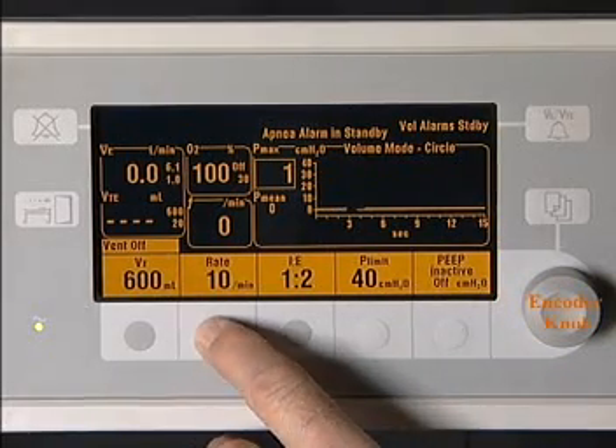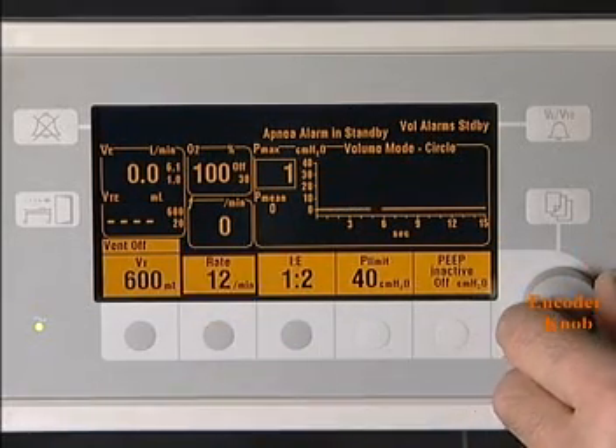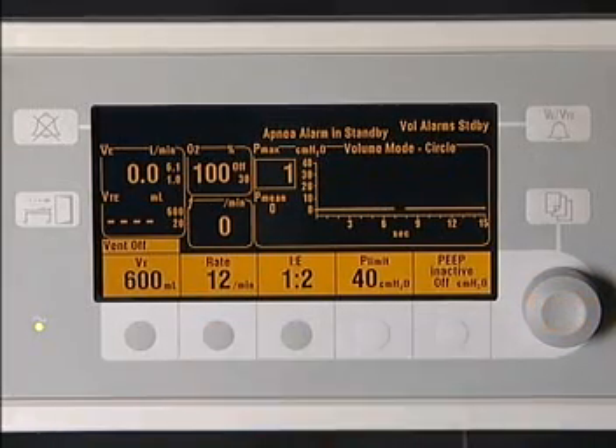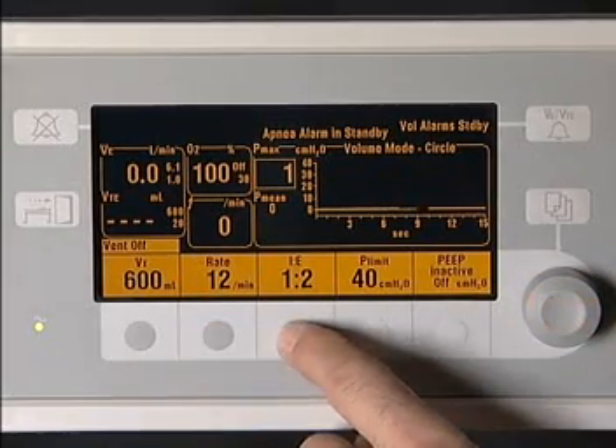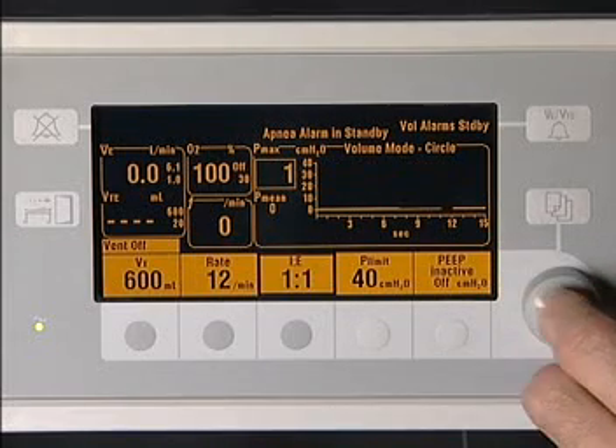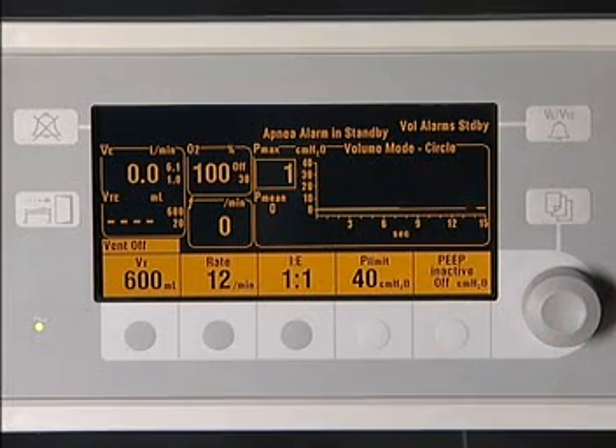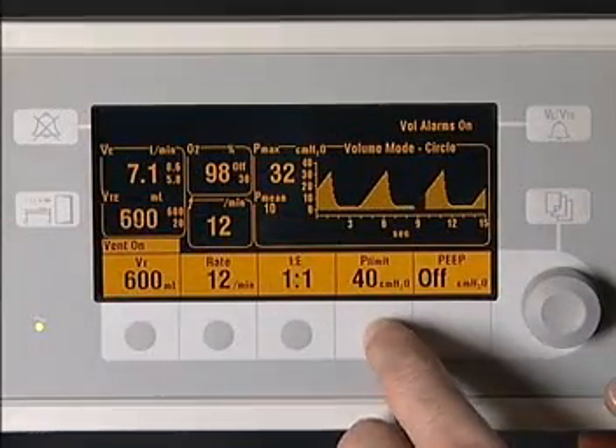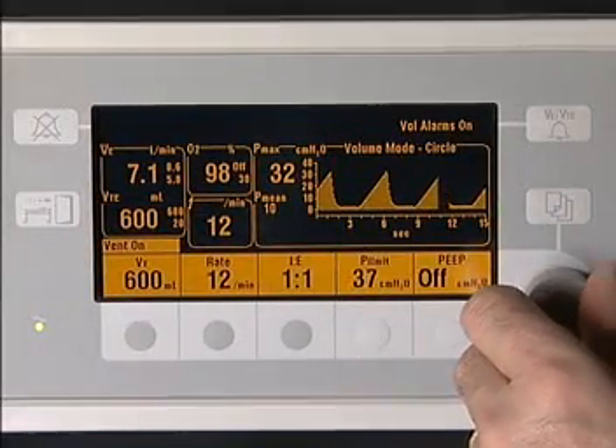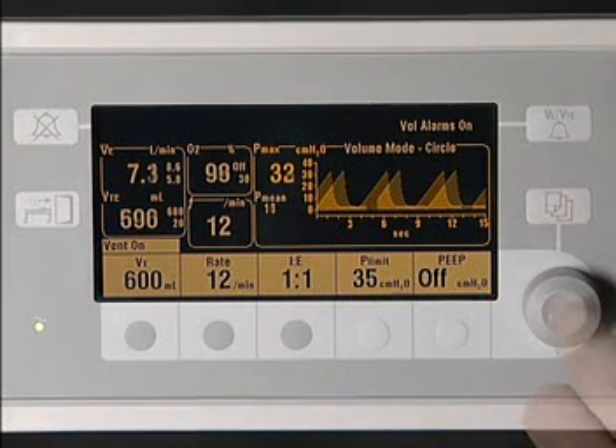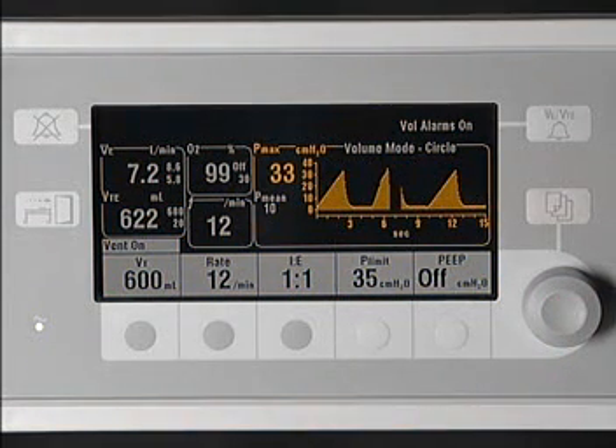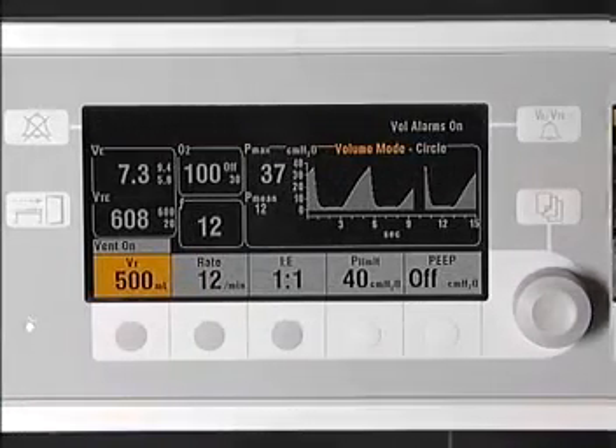Since the ventilator is electronically controlled, the settings can be preset before attaching the patient. The parameter to be set is activated by pressing the key below it, adjusting with the encoder knob, and confirming with either a press of the encoder knob or the selection key. The user controls are located along the bottom of the ventilator control module and will usually be set from left to right. The pressure limit, when reached, will cause the ventilator to immediately end the inspiratory cycle.